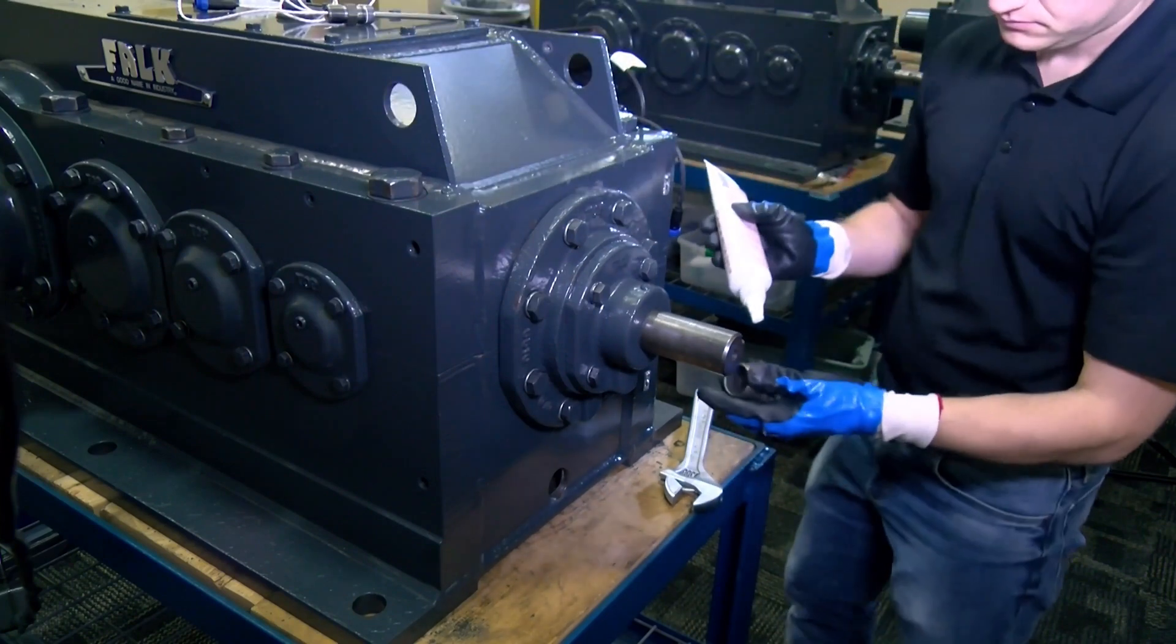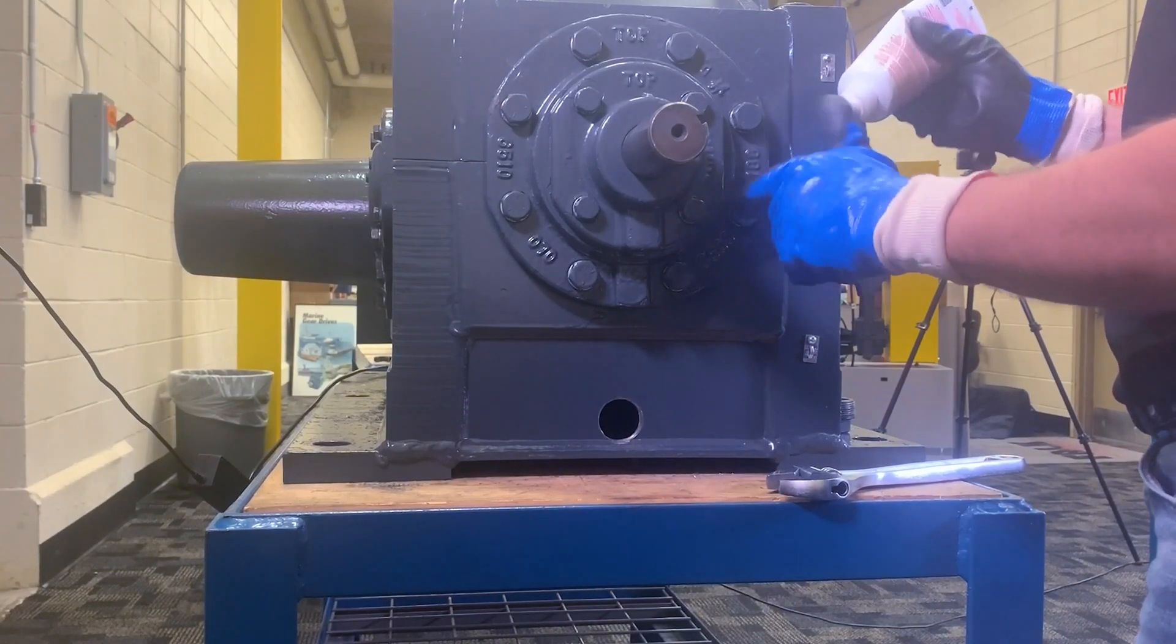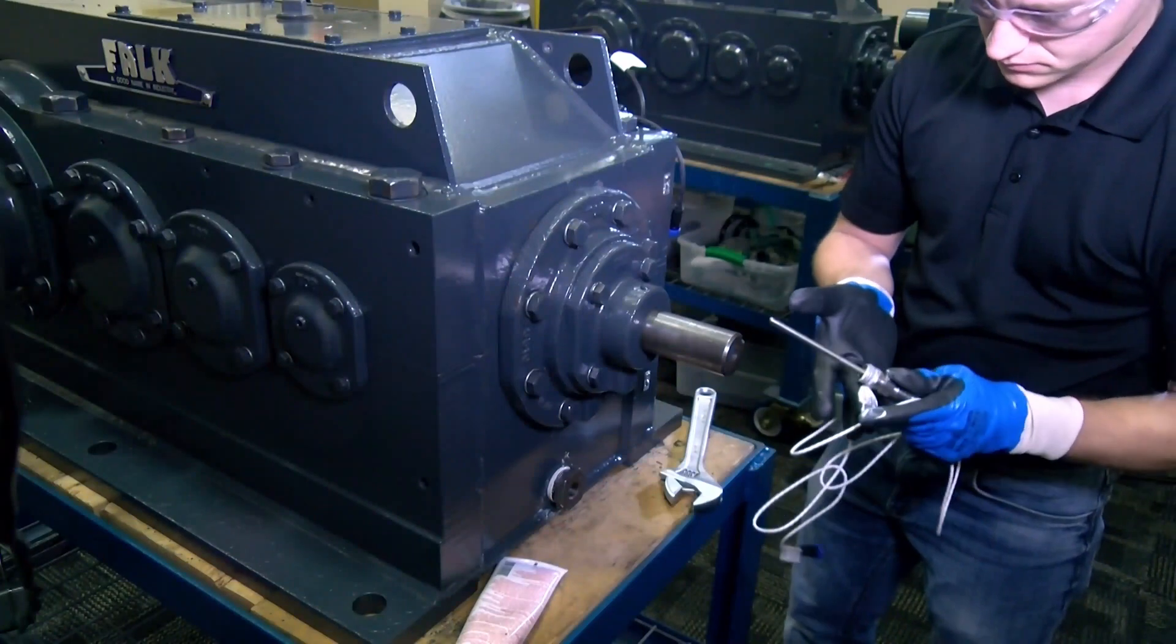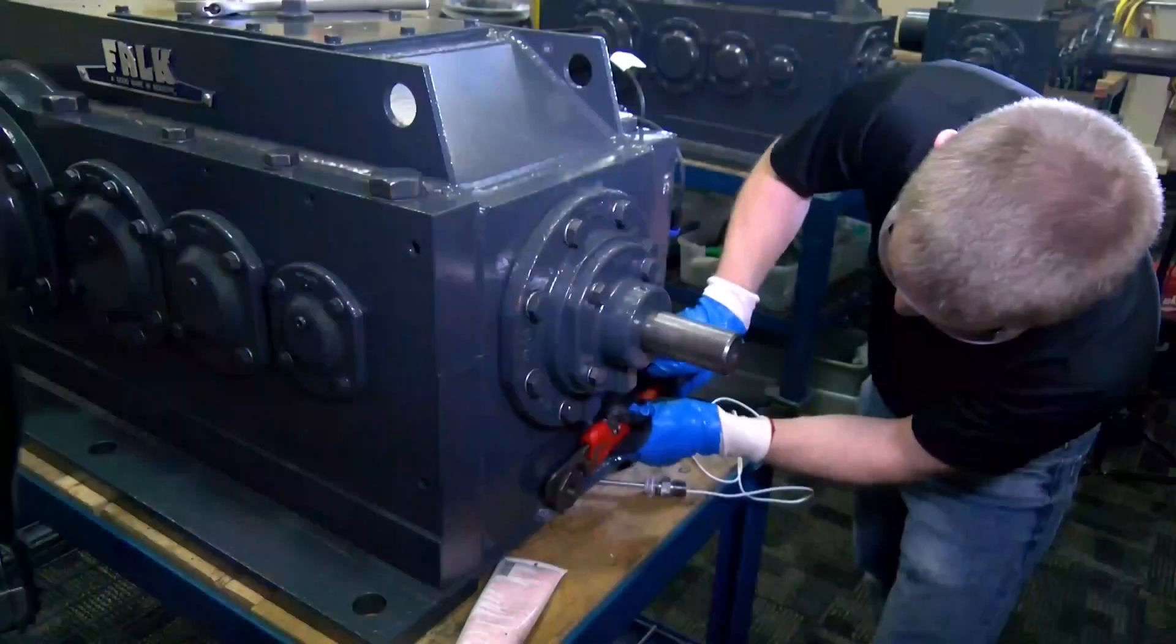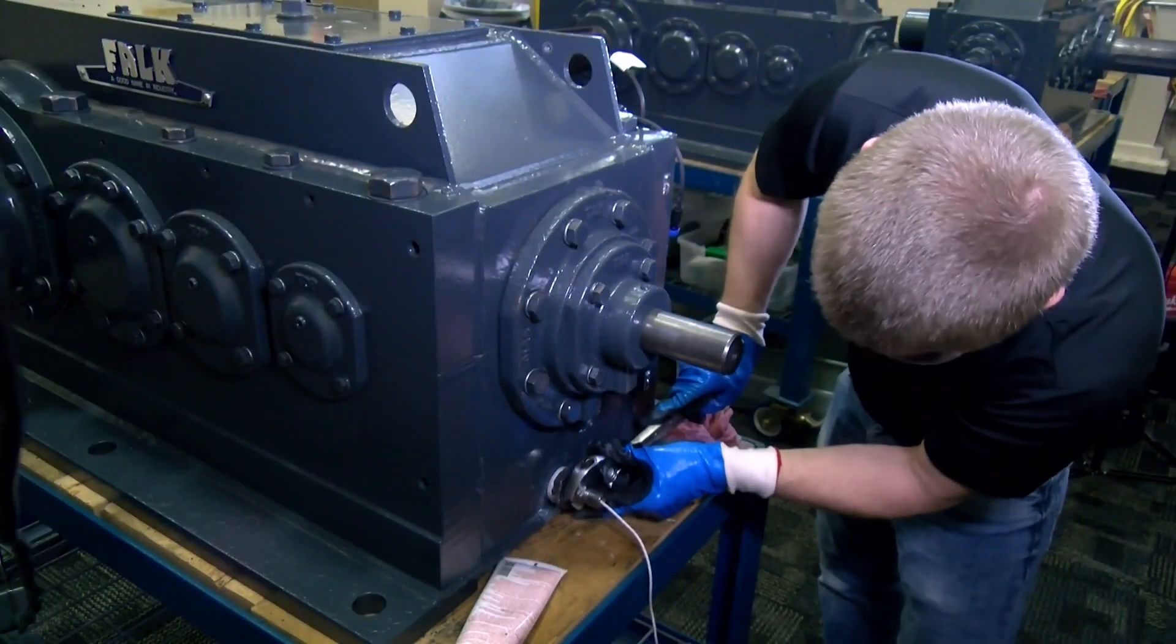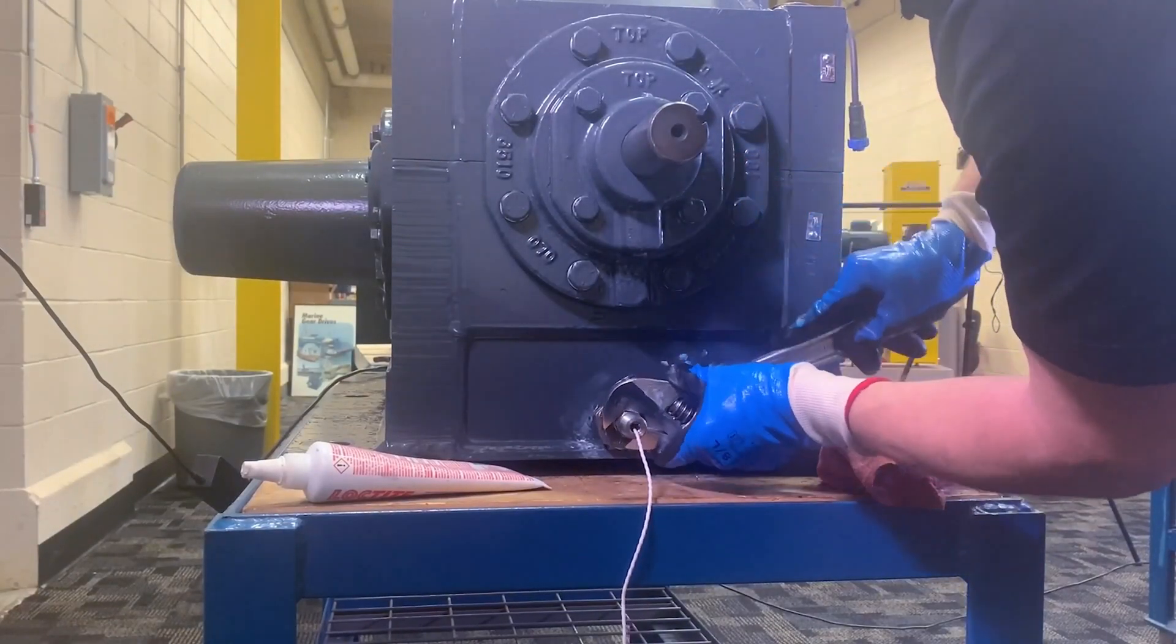Three bushings are included in the 1010 universal kit. Select the proper size based on the gear drive you are installing the kit on. Apply pipe joint compound to the threads on the bushing and temperature sensor. Install the bushing into the drain port and then install the temperature sensor into the bushing.